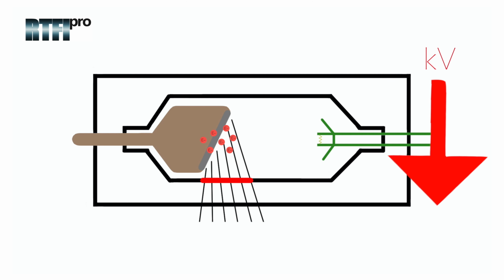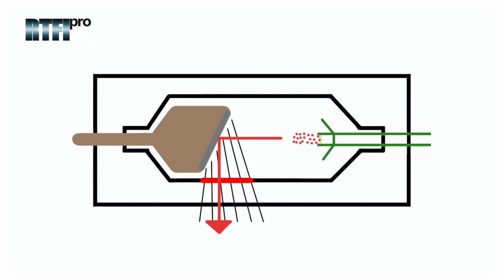As mentioned previously, the quantity of electrons can be controlled by increasing or decreasing the mA. Therefore, this determines the number of electrons traveling to the anode. When electrons travel to the anode, they result in a sudden stoppage with the interaction of the atoms of the tungsten target. This atom interaction will create energy in the form of X-rays that consist of both a diverging beam and a central beam.